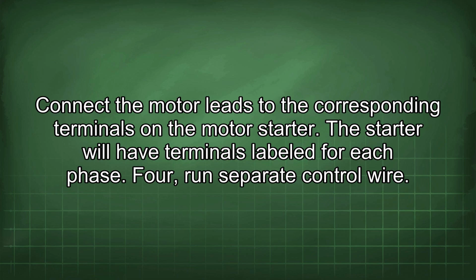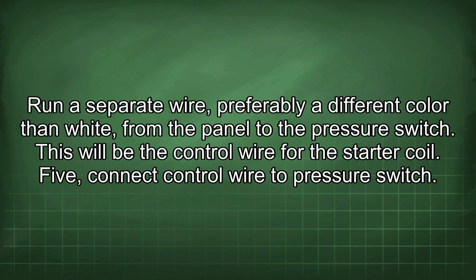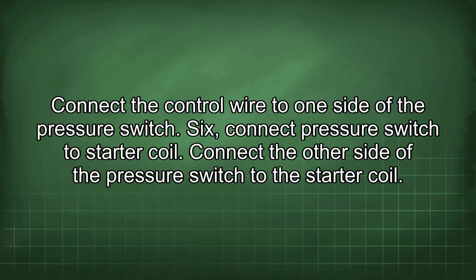4. Run separate control wire. Run a separate wire, preferably a different color than white, from the panel to the pressure switch. This will be the control wire for the starter coil. 5. Connect control wire to pressure switch. Connect the control wire to one side of the pressure switch.